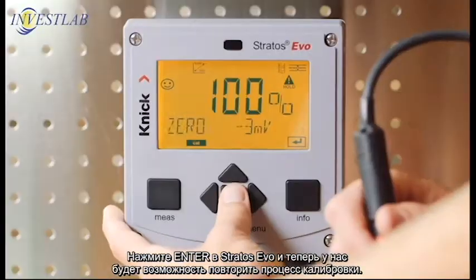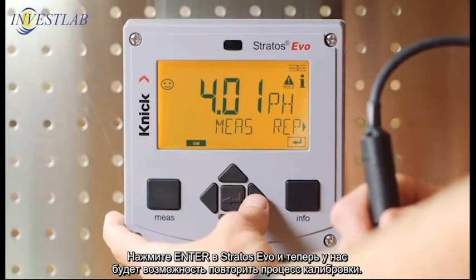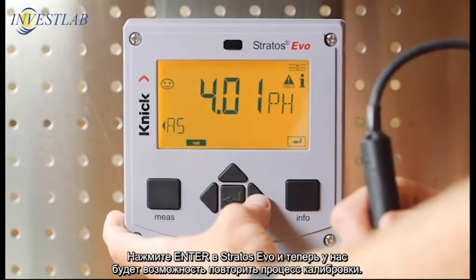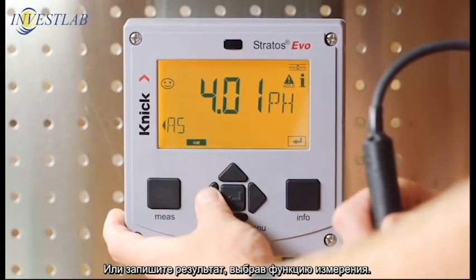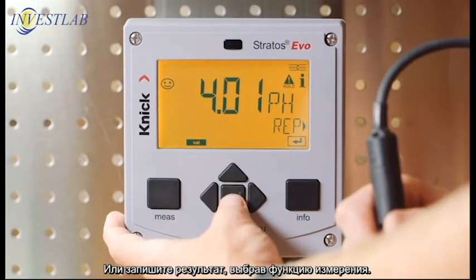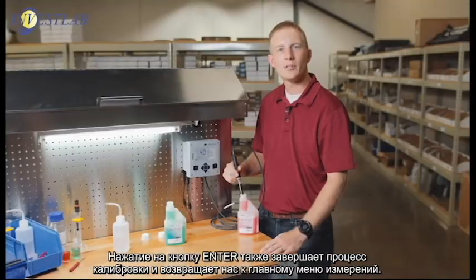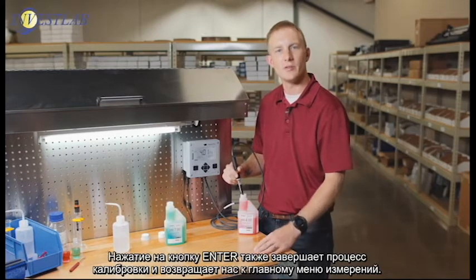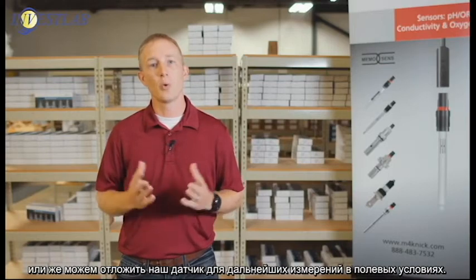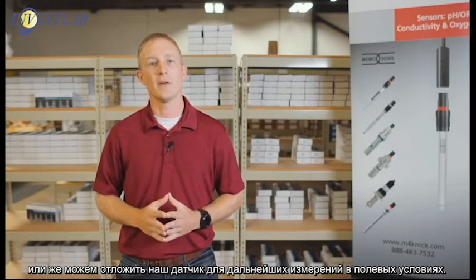Press enter, and the Stratos Evo will now give us the opportunity to repeat our calibration process or write the calibration to our sensor by selecting measure. Pressing enter on measure also finalizes the calibration process and returns us to the main measurement screen.